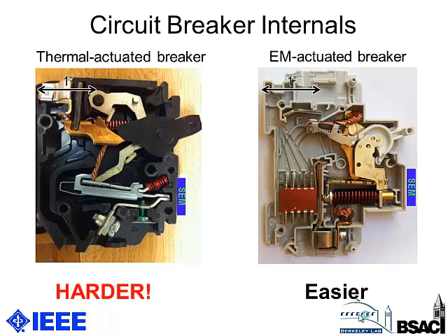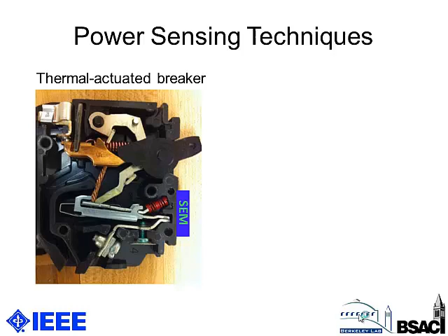So now I'd like to tell you the power sensing techniques we're using for our sensor. So we're sensing the circuit breaker's line voltage capacitively. So here I've highlighted a capacitance that is formed between the conductor in the circuit breaker and the SEM device itself. And a current is induced through this capacitance, which is proportional to the derivative of the line voltage on the circuit breaker. And so this current is then sensed by the SEM sensor using the analog front-end circuit you can see on this slide. And so it's sensed and amplified, and then an ADC digitizes the signal for subsequent processing.